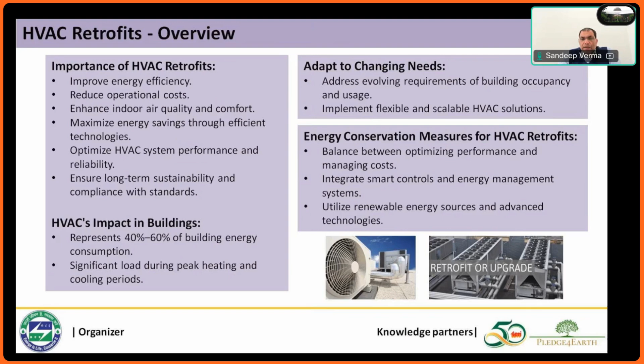A lot of work has been done of late. Though the concept was there, because of other considerations we were not able to enhance the efficiency of our air conditioning systems. Now, with the advent of high efficiency screw compressors, and variable frequency drives which can control the speed of the motor attached to your air compressors in a much finer way, you can optimize the consumption of your air conditioner. What you see here are the inverter ACs. They are nothing but air conditioners fitted with the VFD system. And for ventilation, there are various types of ventilation strategies which we'll talk about. Similarly for heating also.